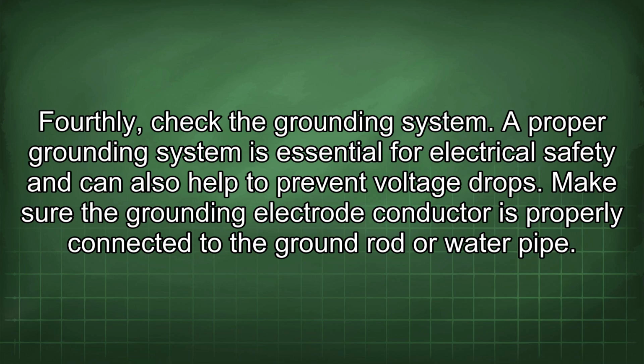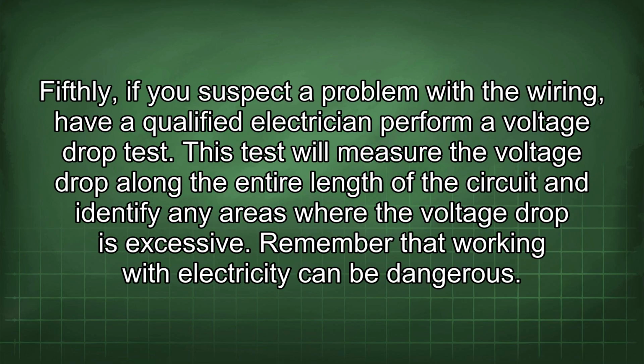Make sure the grounding electrode conductor is properly connected to the ground rod or water pipe. Fifthly, if you suspect a problem with the wiring, have a qualified electrician perform a voltage drop test. This test will measure the voltage drop along the entire length of the circuit and identify any areas where the voltage drop is excessive. Remember that working with electricity can be dangerous.